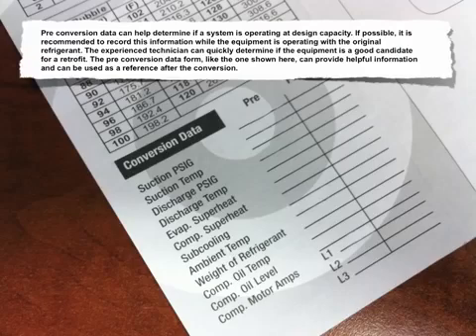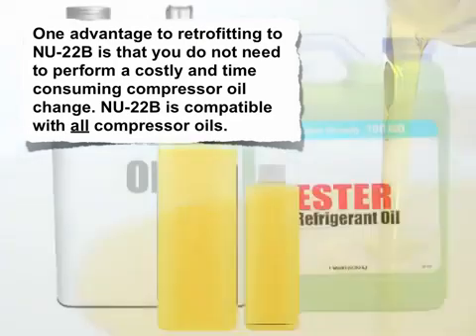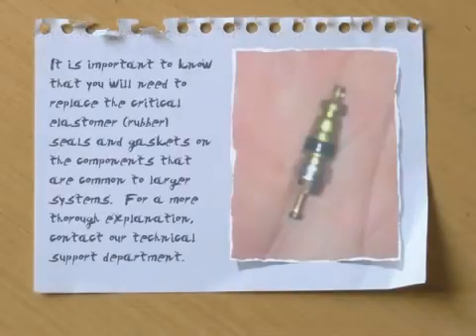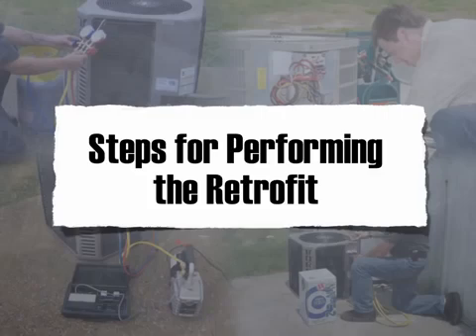The preconversion data form, like the one shown here, can provide helpful information and can be used as a reference after the conversion. One advantage to retrofitting to NU-22B is that you don't need to perform a costly and time-consuming compressor oil change. NU-22B is compatible with all compressor oils. It's important to know that you'll need to replace the critical elastomer rubber seals and gaskets on the components that are common to larger systems. For a more thorough explanation, contact our technical support department.